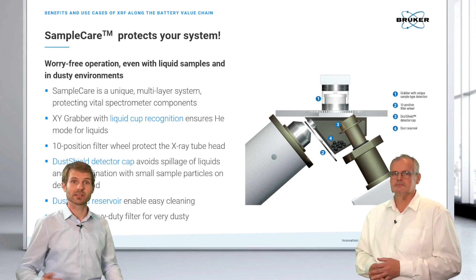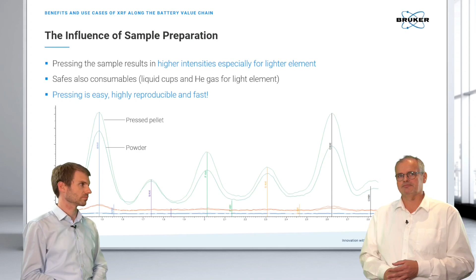Exactly. Then, of course, we talked about the fact that we can work with loose powders, and that's the very straightforward way. In the moment where you receive the material and we want to be a little bit more accurate, with a little bit more precision, it might be useful to press the sample into a stable pellet, which is just an investment of 1 additional minute. You can see the effect here comparing the two spectra. The lower one is the loose powder, and the top one is the pressed pellet spectrum. There is an additional plus in intensity, because we are compacting the powder and getting rid of the air in between. This leads to a higher intensity.